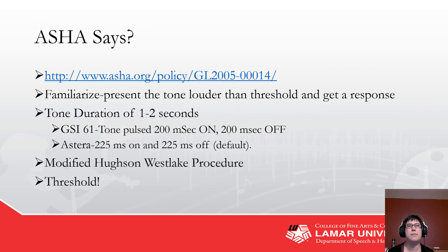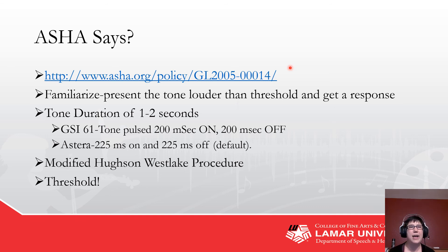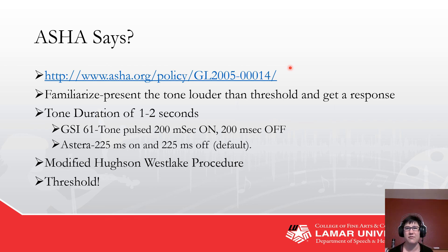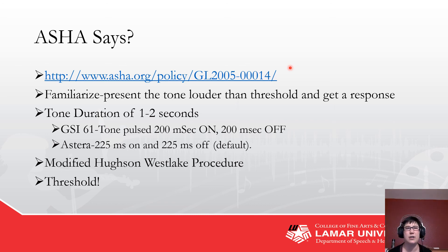What does ASHA say? Their methodology is to familiarize by presenting a tone louder than threshold to get a response. Tone duration needs to be one to two seconds — for the GSI 61 with pulsed, it's 200 ms on, 200 ms off; for the Astera it's 225 ms on, 225 ms off. I like to use pulsed because you can count about four pulses and map that out to get one to two seconds. If you have tinnitus, pulsed tones make it easier to hear.